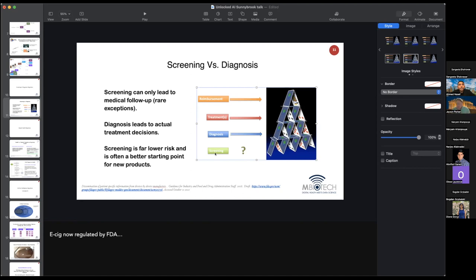A common problem occurring in the digital health space right now is that a lot of startup companies try to position their product idea as a new diagnostic tool. The burden of evidence for a new diagnostic tool is going to be extremely high. So oftentimes it's better to position your new technology as a screening tool. That way you're going to have a much greater likelihood of approval by the FDA. And if you want to go for a diagnostic indication, you can do that down the road when you have more money and can conduct more robust testing.